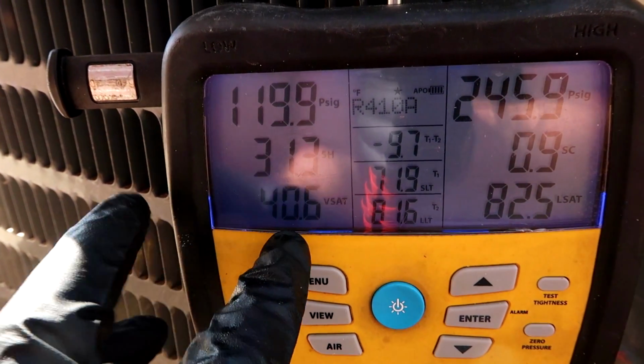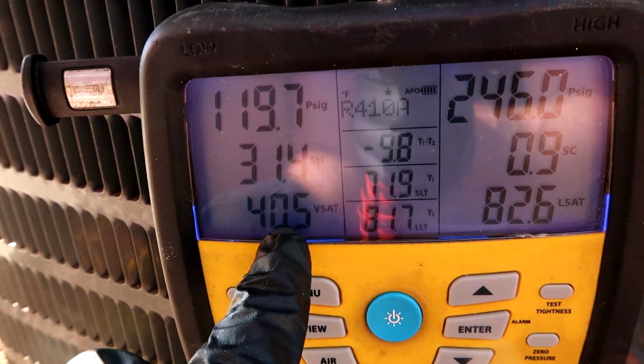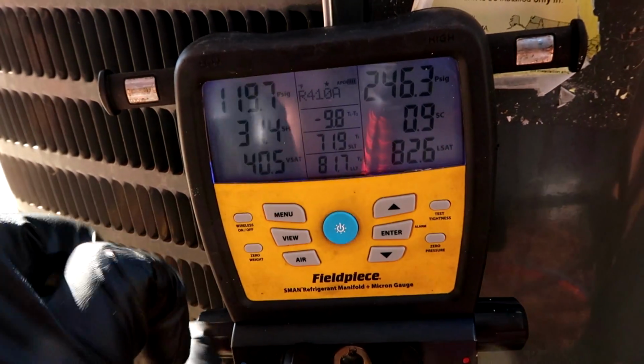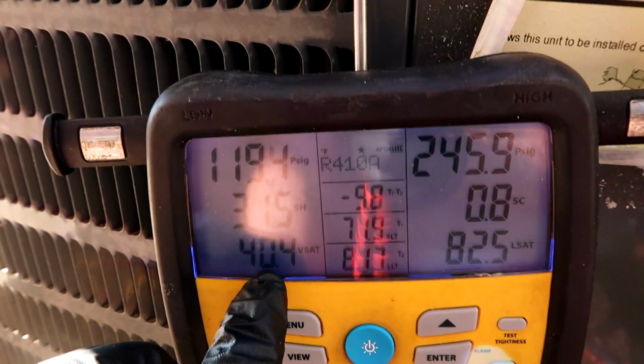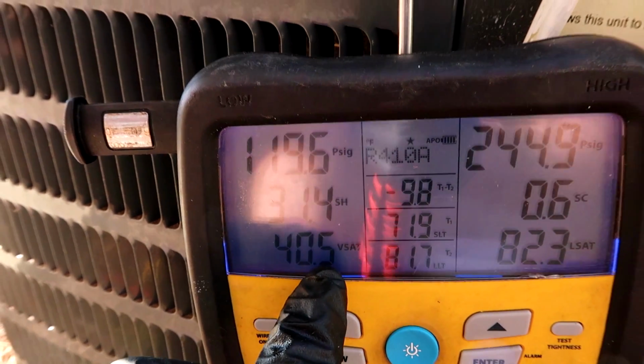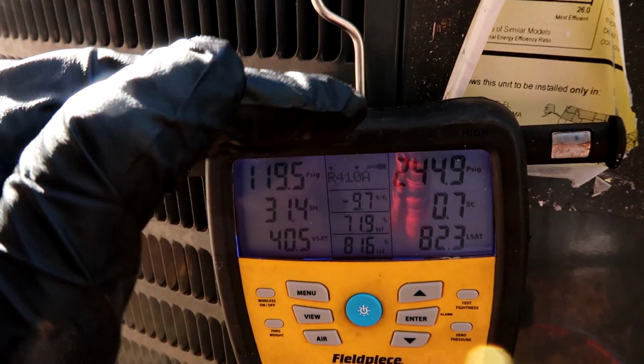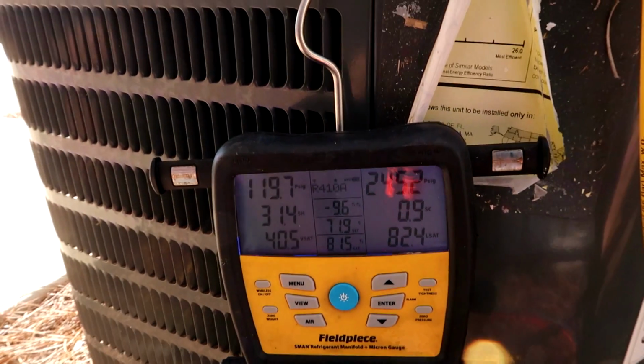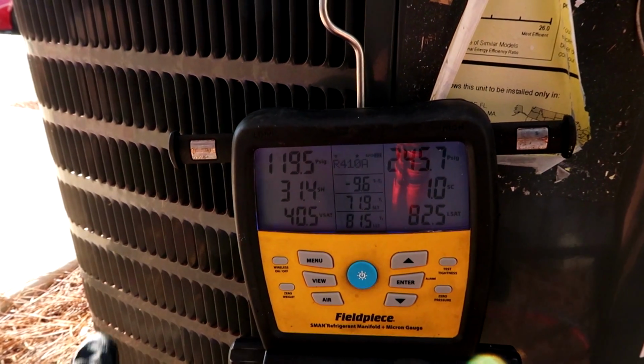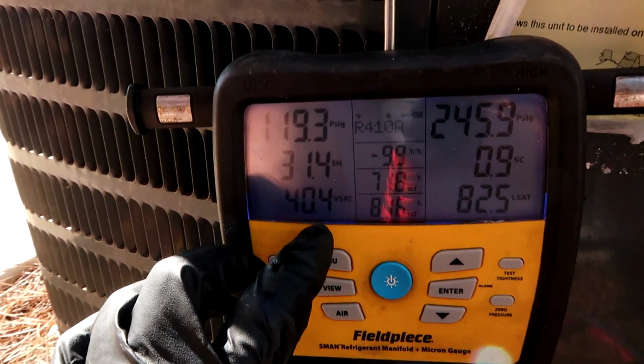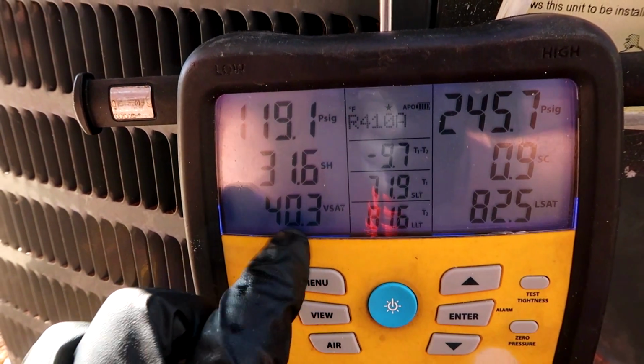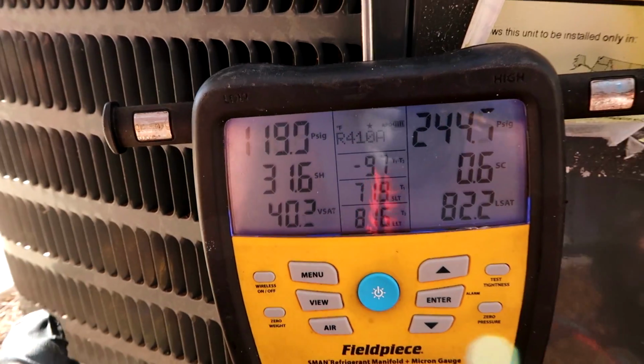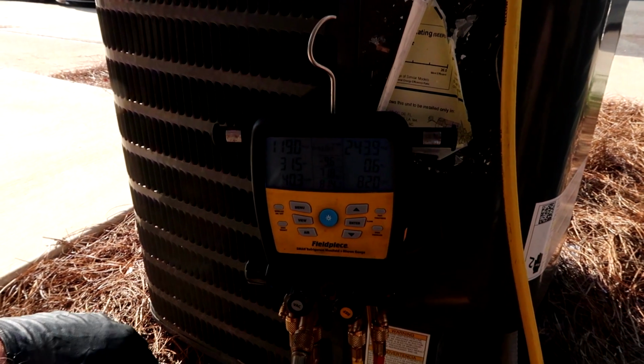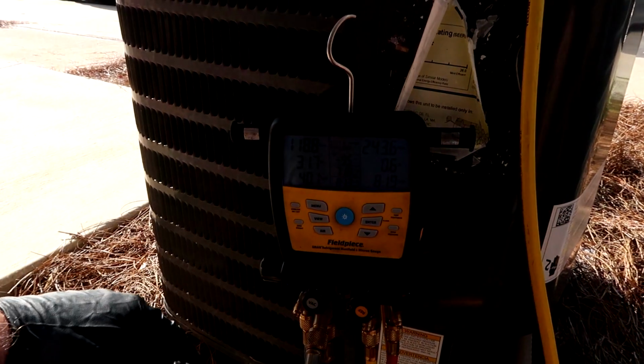There was one time, a long time ago, I could not get the saturation above 32. I just kept adding refrigerant. Would not go above 32 degrees on the saturation. And what happened was the fire damper closed in the plenum on the unit. So watch out for that. If you're ever dumping refrigerant in there, you just keep dumping and this number doesn't change, go check the fire damper in the plenum. Yeah, I had an airflow issue. So there's a little tech tip for you. Could be something else as well, but that was a tricky one for me.